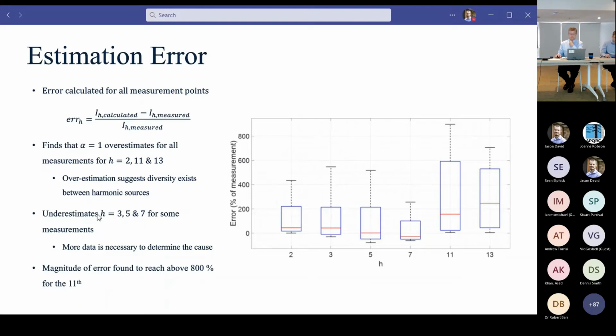What we can see is that there are some underestimations, and that's what I was referring to previously, where there are some limited number of measurements that fall below that black line for the 3rd, 5th, and 7th. But we certainly need a little bit more data and thinking around exactly where this is coming from. The maximum error that was detected was above 800%, bordering on 900% for the 11th order.